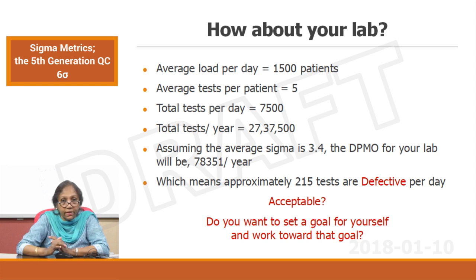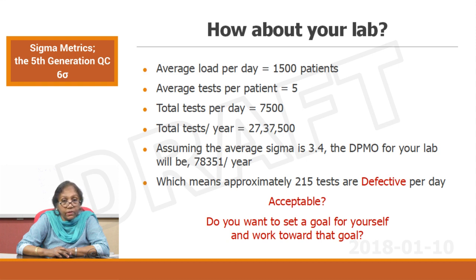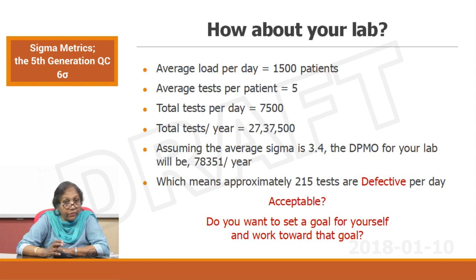We are going to take that figure of 3.4 sigma — the number of errors we are making — and convert it into the number of defective reports you could be giving per day. Average load per day: I am assuming 1500 patients in a medical college laboratory, and per patient you are doing 5 tests — total of 7500 per day. Total tests per year becomes 2,700,000 per year, which converts to 78,351 defects per year.